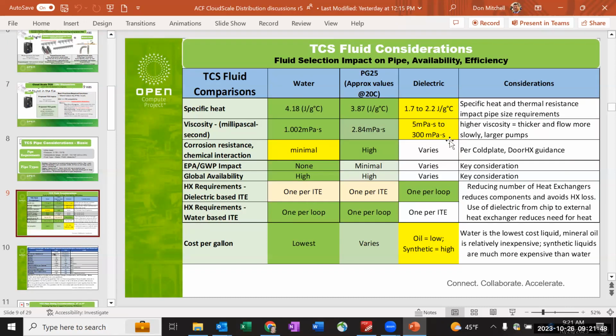Do we actually have to change out, flush and purge? And are there things we need to do specifically to make the liquid better? So let's go back to the beginning of your scenario. Your scenario with the rear door heat exchanger is cold plate cooled. The scenario with the heat exchanger right now is starting out with cold plate or door heat exchangers. You're going to be looking at water or PG25.